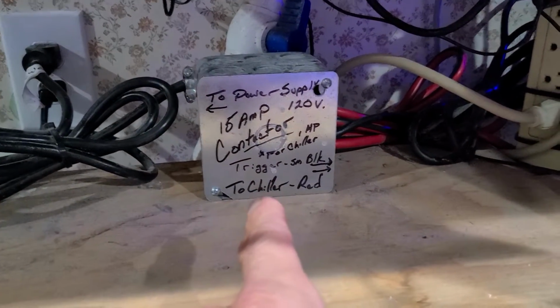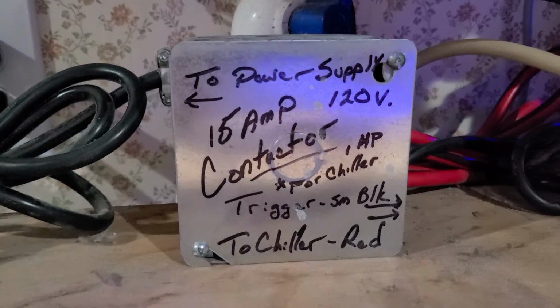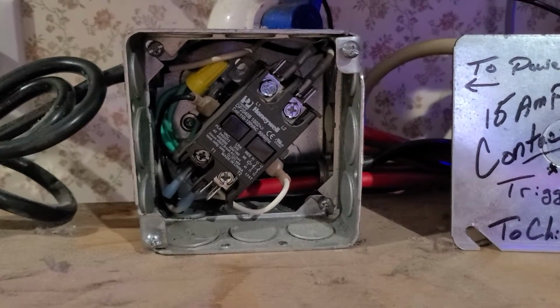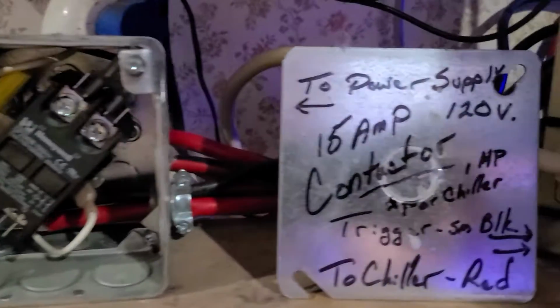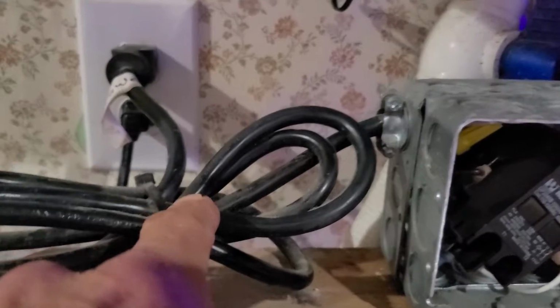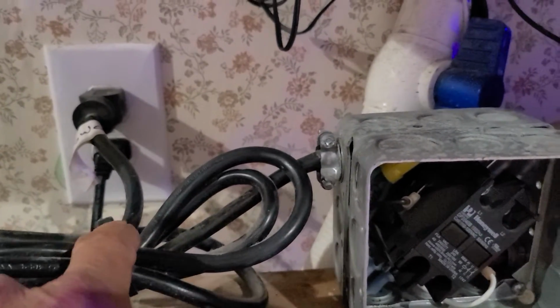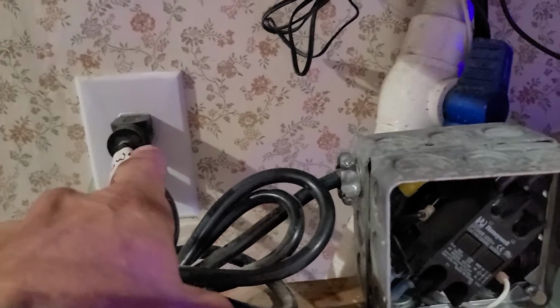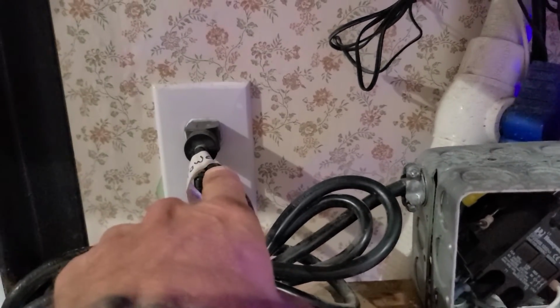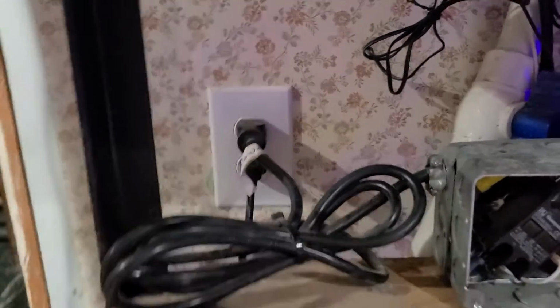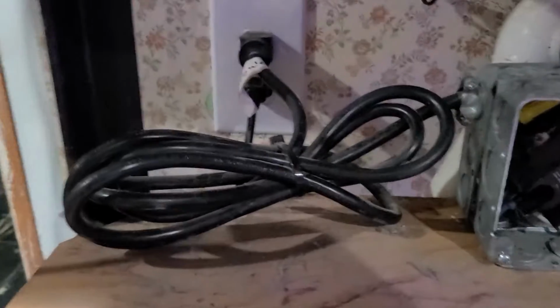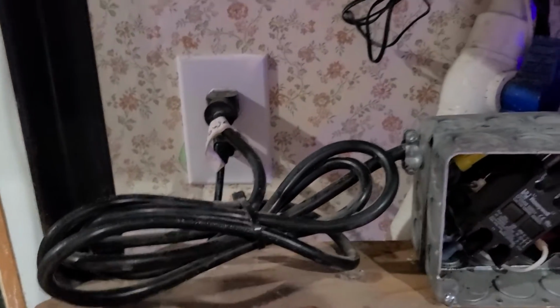I'm going to pause here for a second while I pull this off so you can take a look inside. Okay, now I got the cover off. You can kind of read the cover. I have this, which is the main power supply. It runs all the amperage. I have it running to a dedicated 20 amp outlet that I basically wired into the house a long time ago. Basically 2 dedicated outlets, both of them 20 amps, but I run the chiller on one circuit basically by itself.